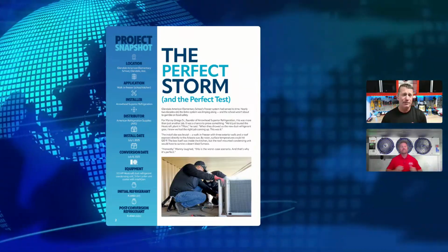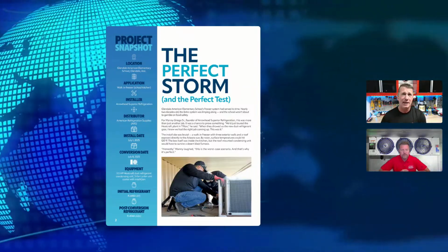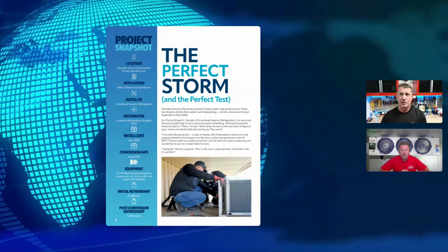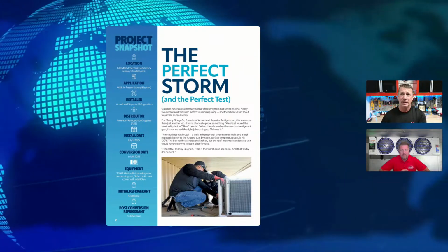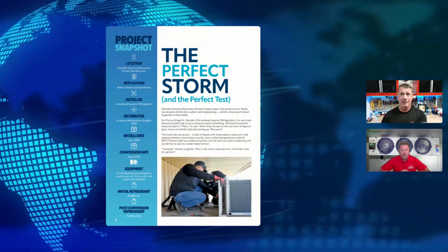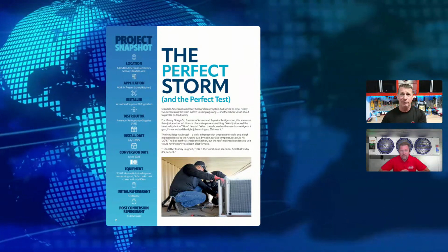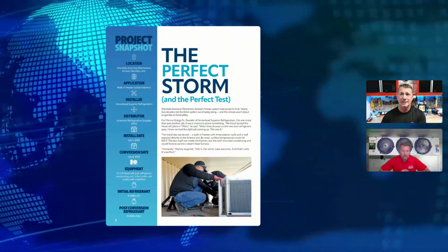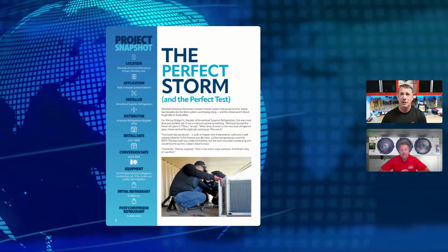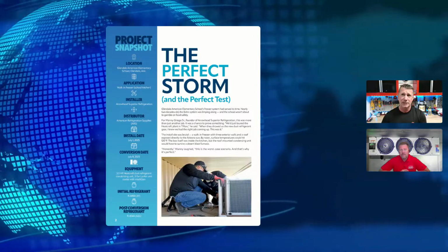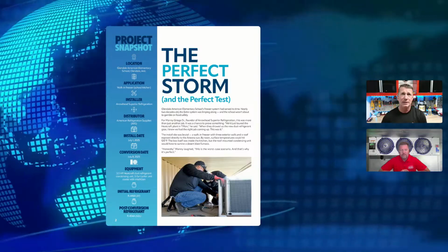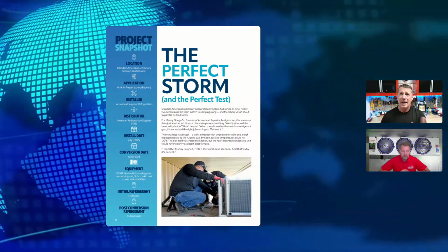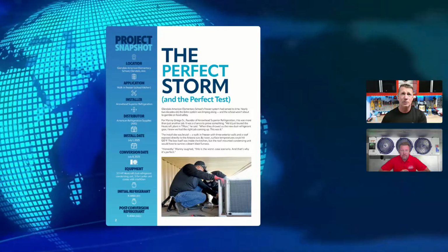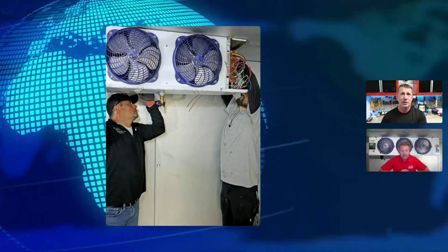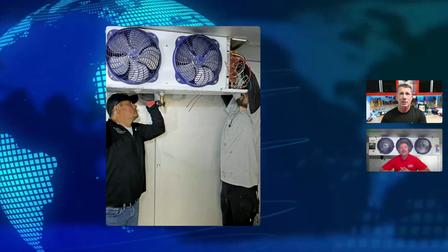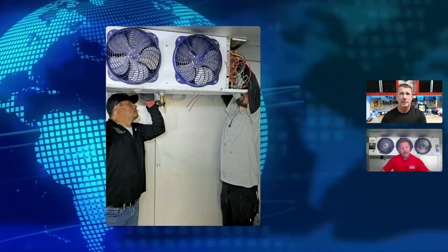And I myself am an advocate for, even if we're doing an A1 installation with an A2L compatible piece of equipment, it's worth installing it because at the least we're adding some refrigerant leak detection to that system, right? It may not be tuned as well as an A2L refrigerant is for detection, depending on the sensor that's used, but at least it's adding that additional security. And we're also getting all the modern controls that go along with that system. Yes, absolutely. All right, so this is that case study.